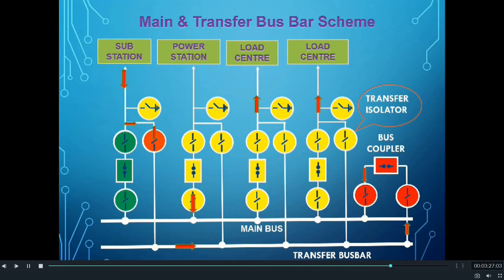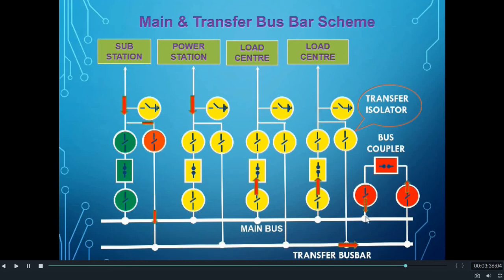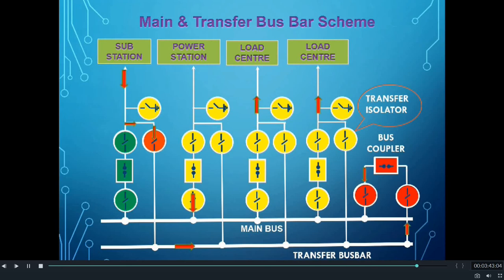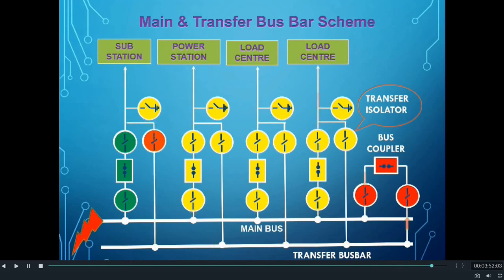So with this arrangement, we are basically connecting the feeder to the main busbar through the transfer busbar and the bus coupler. Hence, in this scheme, when the main circuit breaker of a feeder becomes faulty, the feeder can still be connected to the busbar with a short outage and work normally as before. However, the problem still lies with these busbar schemes in case of a busbar fault. In case of a busbar fault, all the feeders become out and we don't have the scope to overcome the problem.